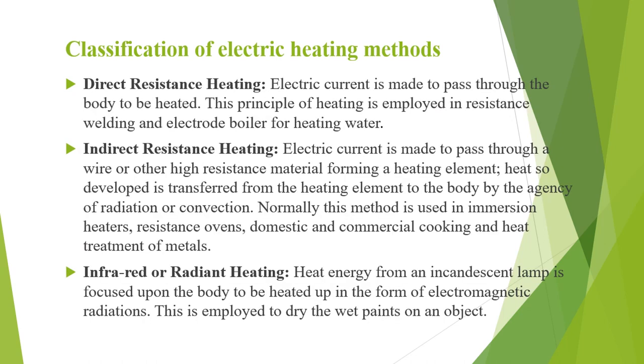Direct resistance heating: in this method, current is made to pass through the body which is to be heated. Application is in resistance welding and electrode boilers for heating water. Indirect resistance heating: in this method, current is made to pass through a wire or other high resistance material which forms the heating element. The heat developed is transferred from the heating element to the body by radiation or convection.